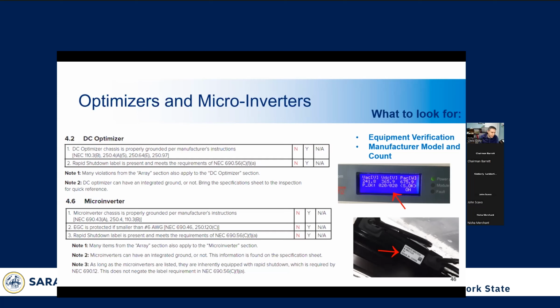And so basically what you want to do within this section is verify that the equipment on the design documents is what's actually installed, and verify the proper grounding and bonding throughout the electrical path. One thing to keep in mind is microinverter systems do meet rapid shutdown requirements. By design, they all have this as a feature, but they do also require proper labeling, which we'll again go over in a little while.